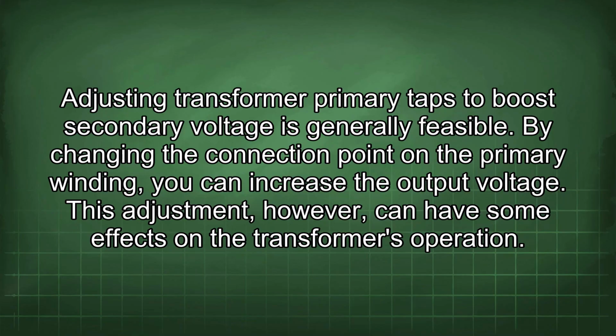Adjusting transformer primary taps to boost secondary voltage is generally feasible. By changing the connection point in the primary winding, you can increase the output voltage. This adjustment, however, can have some effects on the transformer's operation.